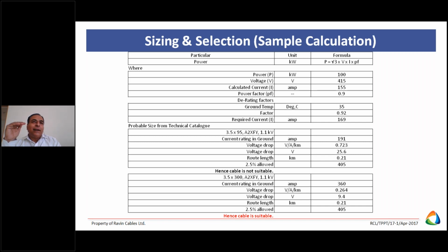Normally, whatever design we are doing, we are considering 100% utilization of the system. But in the cable, we have taken so many safety factors. These are fit-and-forget items. Cables should be sufficient, strong enough so that reliability will be there. So we have considered a lot of factors here. We consider 100% utilization, but at no moment does it go to 100%. Normally it is 60-70%. So we consider all the parameters, reliability, and based on that we select the cables. This is just for the current rating.